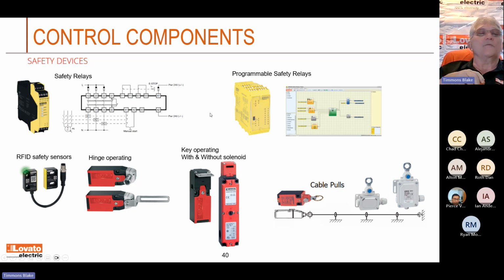We have what we call a programmable relay. There's a few of them out on the market. Some of these gate sensors, that RFID safety gate sensor, are kind of nice because you really only have to run a wire to one side of these things, and there's little coded magnets in the other side. You've got hinged operating switches. Now you notice these are red and they all have a safety certification on them. I can't just put any limit switch on there and expect it to meet safety standards. I had a job one time where a lot of the safety gates were just limit switches. Like, all right, let's get them off and at least get them on there as safety limit switches, and that way we're covered a little bit.